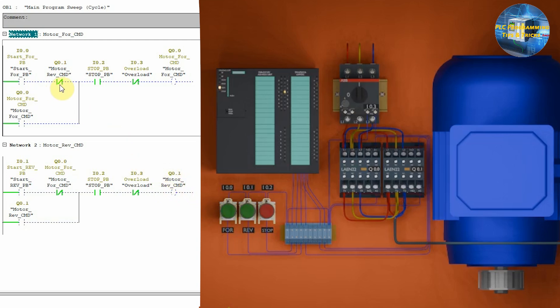So, this means that we can only turn on the motor forward command Q0.0 when the motor reverse command Q0.1 is off.